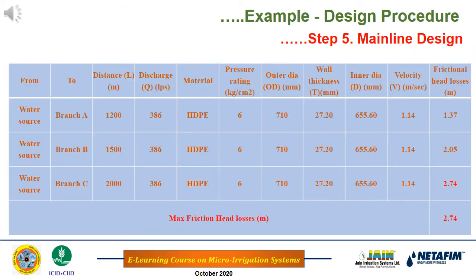To design a main line, prepare a table as shown in this slide. From, to, distance, discharge, material, pressure rating, outer diameter, wall thickness, inner diameter, velocity and frictional head losses. There are 3 branches we propose: branch number A, branch number B, branch number C. Now put the values of these branches and work out frictional head losses in each branch. Among 3 branches, maximum frictional head losses occurs in branch number C, that is 2.74 meter. This 2.74 meter head losses has to be accounted while calculating total head requirement of the pump.